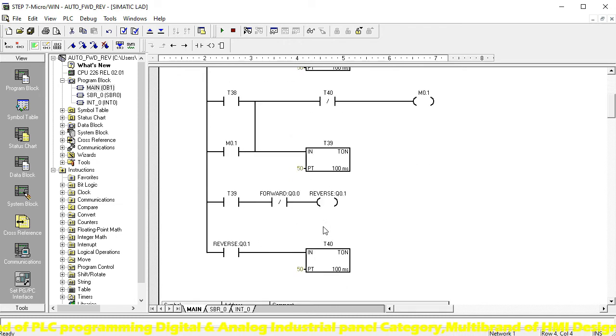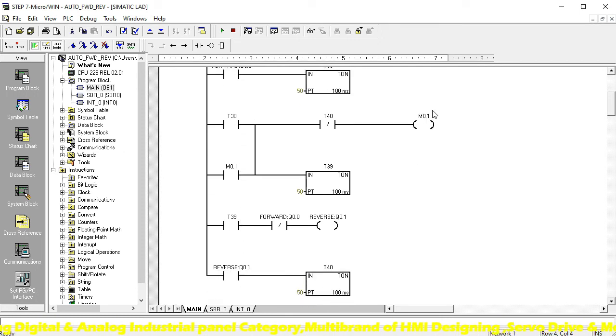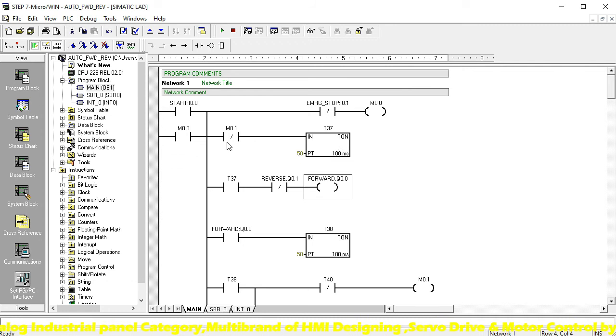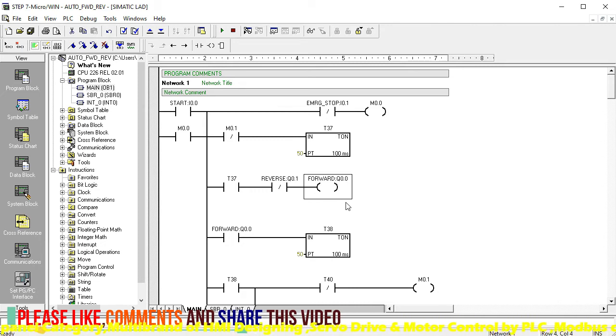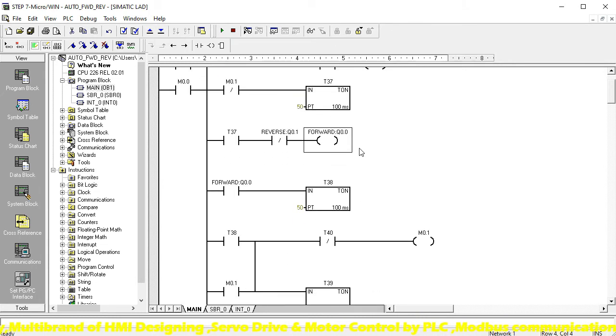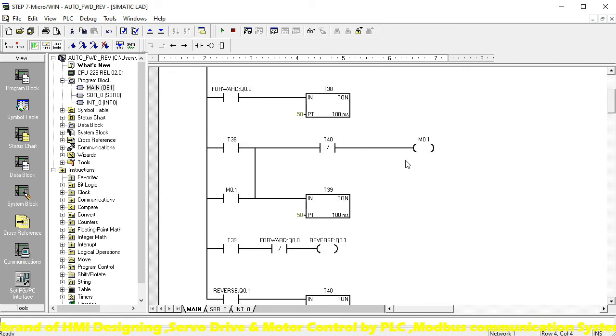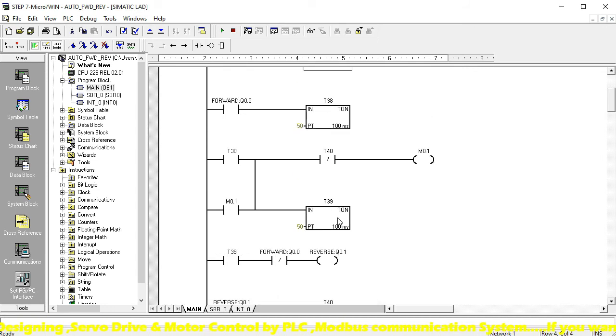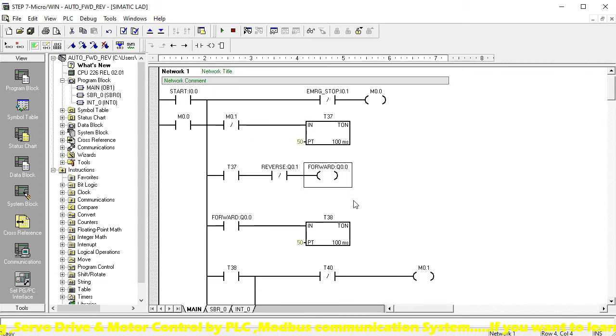After five seconds, when M0.1 relay energizes, all outputs stop, latching occurs, and T39 starts running. Then Reverse turns on. When T40 times out, relay M0.1 turns off, which turns off Reverse. When relay two turns off, the NC contact transfers power, continuing the cycle — because when the device is off, the NC (normally closed) contact works. So the cycle is: five-second initial delay, Forward runs five seconds, off, five-second delay, Reverse runs five seconds, off, then Forward again — very safe operation.